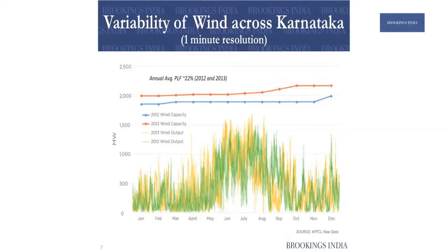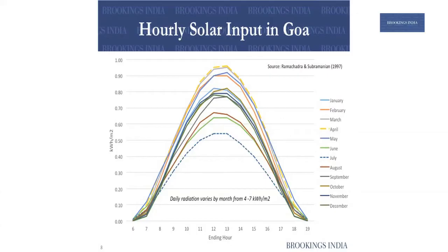This is a very typical load curve from wind — two years of wind data in Karnataka at one-minute resolution. The installed capacity is 2000 megawatts, but wind is very seasonal, occurring in the monsoon season as expected. The average PLF is 22 percent. This shows you what solar looks like — data from a paper on Goa, where hourly between 6am and 7pm you get different outputs. Maximum comes in April, minimum in July, so you get between 4 and 7 kilowatt hours from solar.